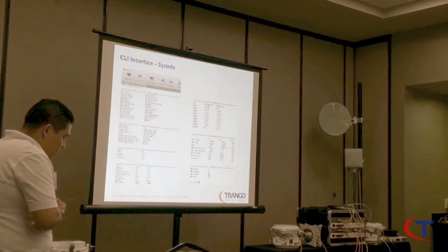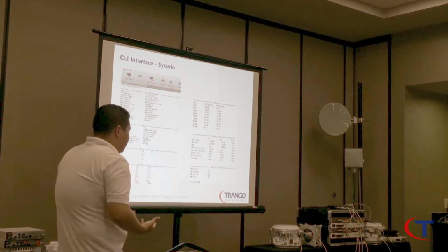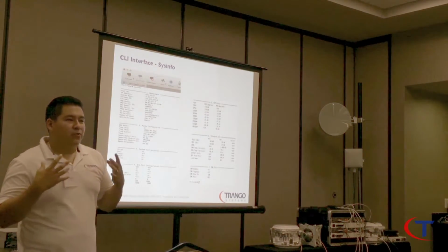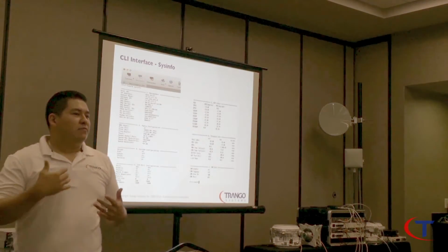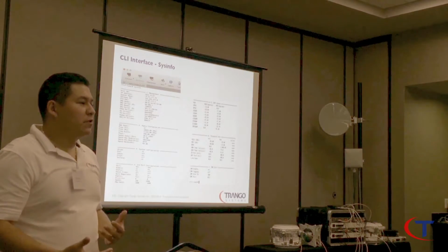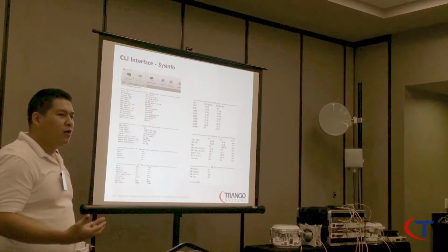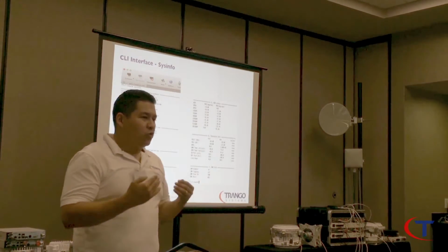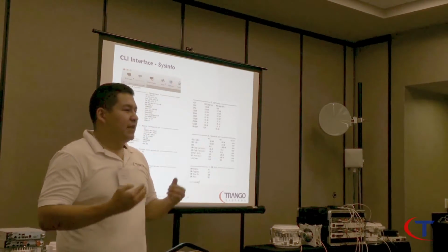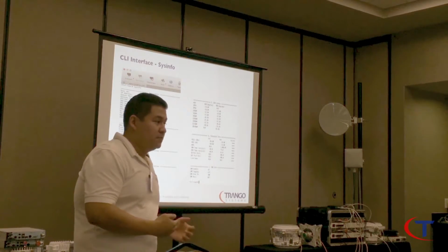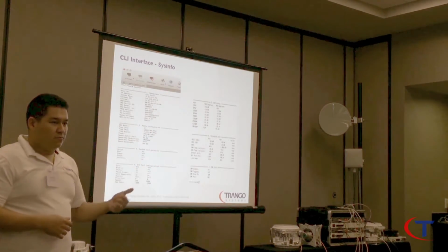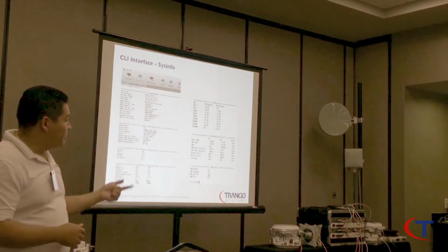Now, we've been talking about the system setup, the actual IP, the management interfaces, but as far as real lab application, we talk all the way about a 1024 QAM link, right? 512, 32 QAM. What actually drives that modulation rate is my MSE value. Okay? Correlation: RSSI has to be a lower negative value, MSE higher.